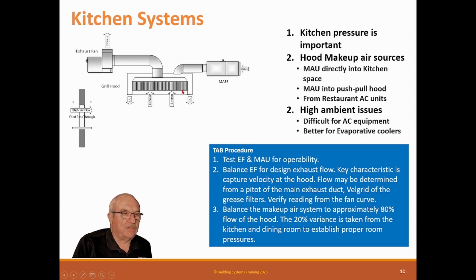Velgrid can be done here. It's not too bad when you do this. And this hood may be a single side or maybe dual side, whichever, or you can just pitot the duct, either one. The problem with pitot in this duct, it may be a welded duct. It probably will be a welded duct. And so you can't use plastic plugs in a welded duct. It'll have to have a cap pitot plug that's designed for steel.